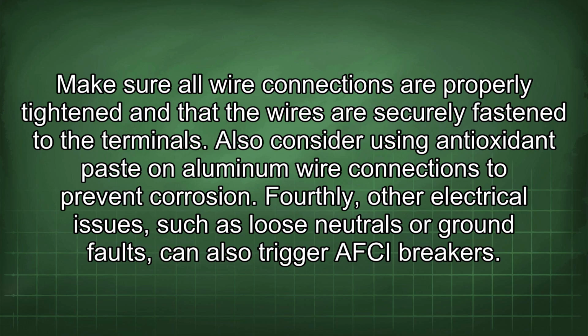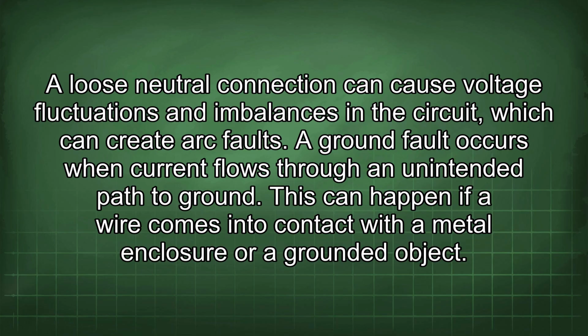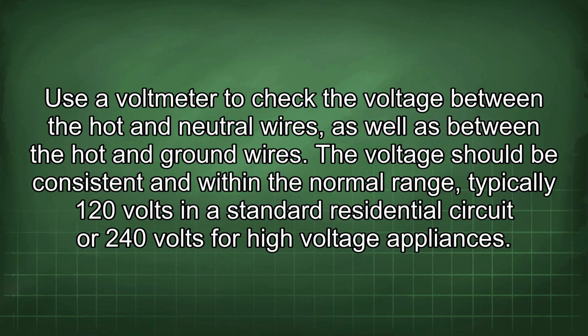Fourthly, other electrical issues, such as loose neutrals or ground faults, can also trigger AFCI breakers. A loose neutral connection can cause voltage fluctuations and imbalances in the circuit, which can create arc faults. A ground fault occurs when current flows through an unintended path to ground. This can happen if a wire comes into contact with a metal enclosure or a grounded object. Use a voltmeter to check the voltage between the hot and neutral wires, as well as between the hot and ground wires. The voltage should be consistent and within the normal range, typically 120 volts in a standard residential circuit or 240 volts for high voltage appliances.